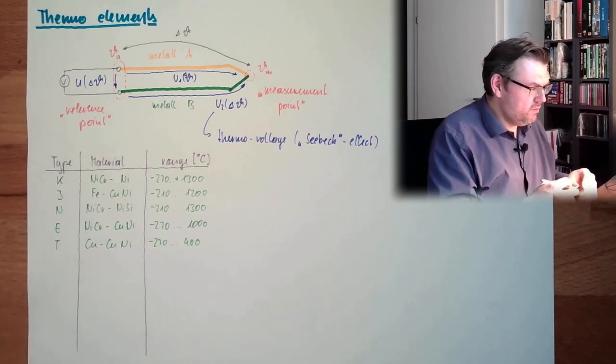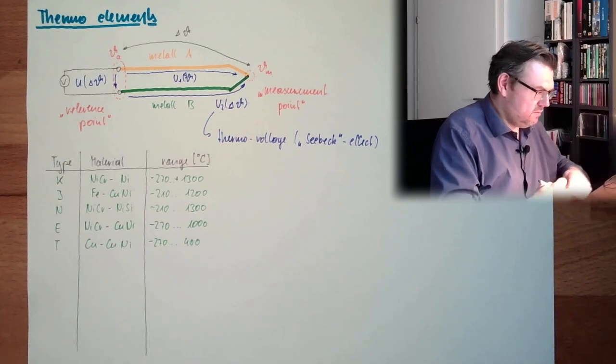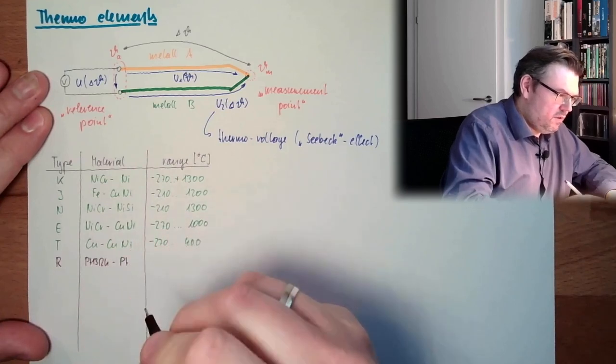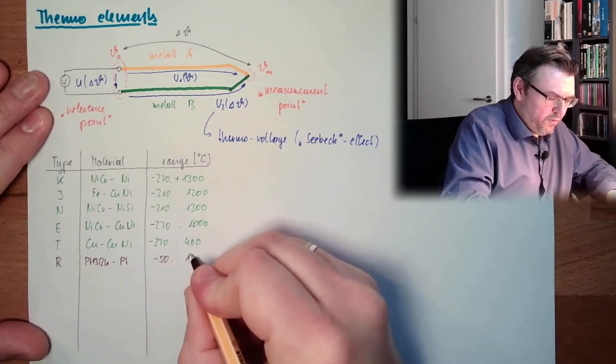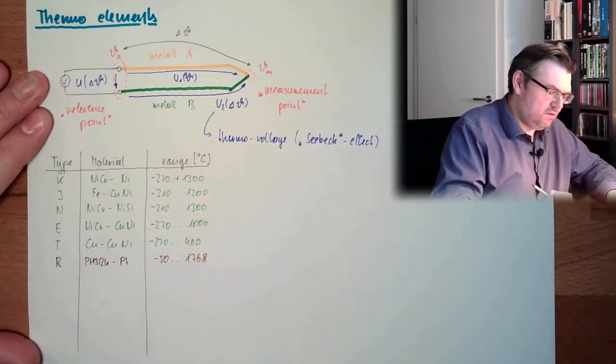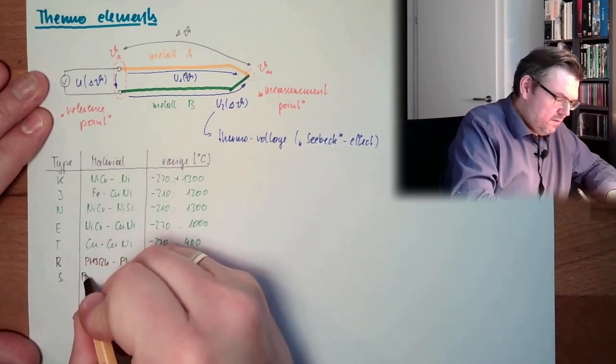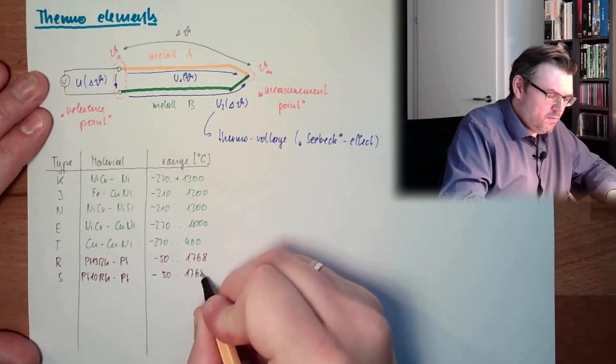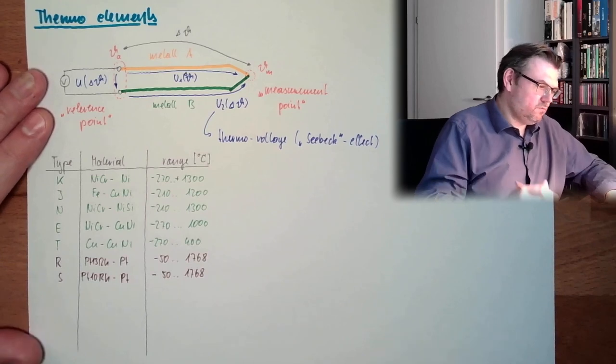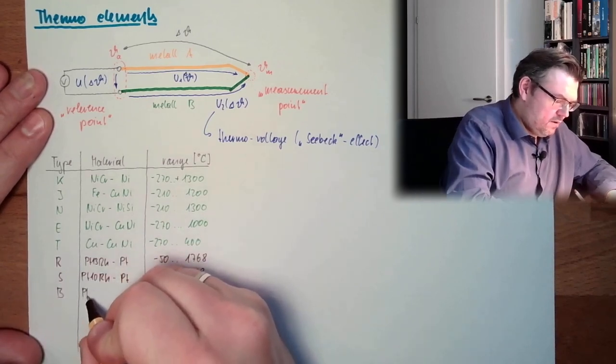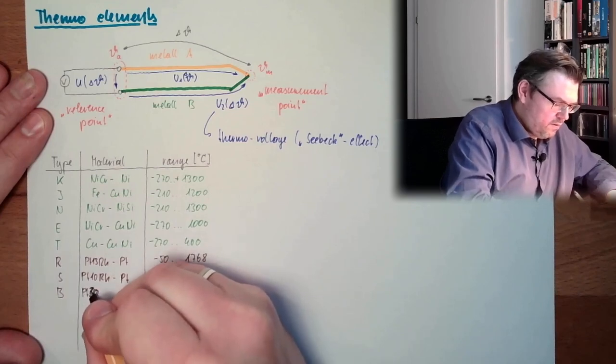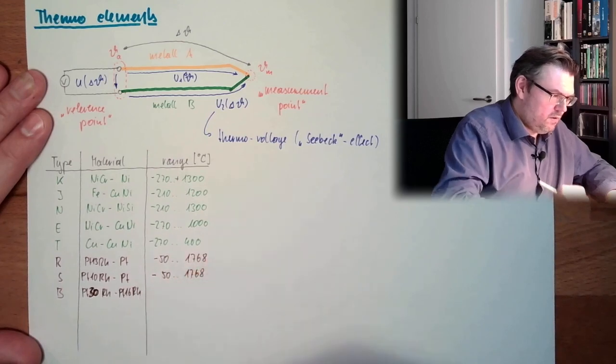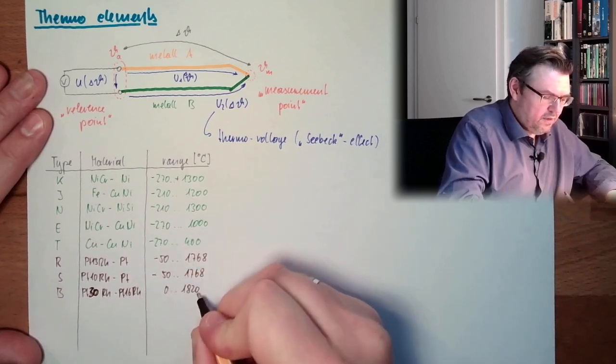And also very often used are these platinum things. Platinum rhodium R, platinum 13 rhodium, platinum. This goes from minus 50 to 1768, so much higher than the others. Also S, platinum 10 rhodium, platinum. Then there would be type B, platinum 30 rhodium, platinum 16 rhodium. This goes from 0 to 1820.